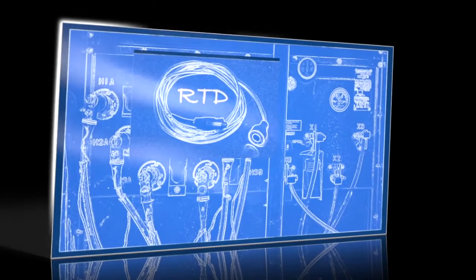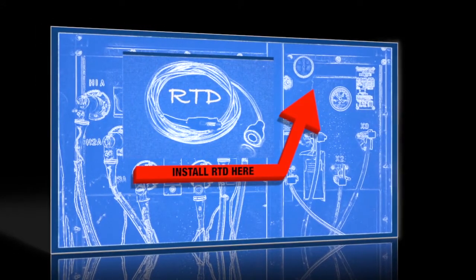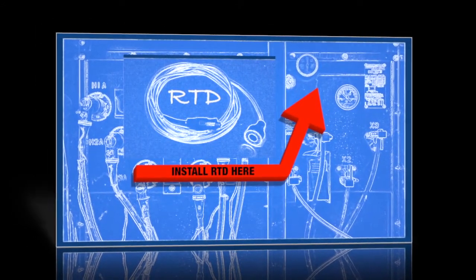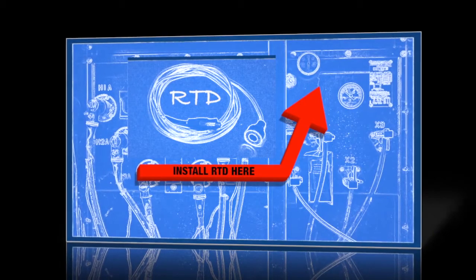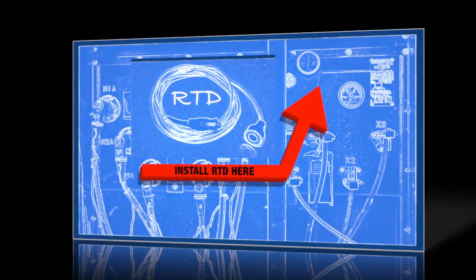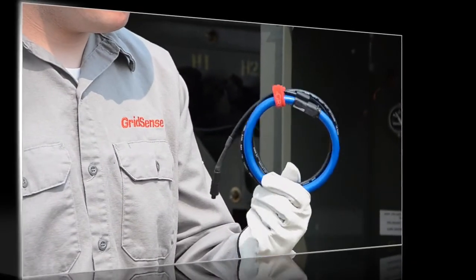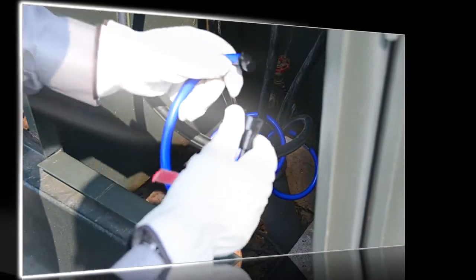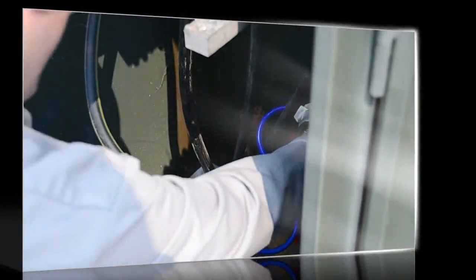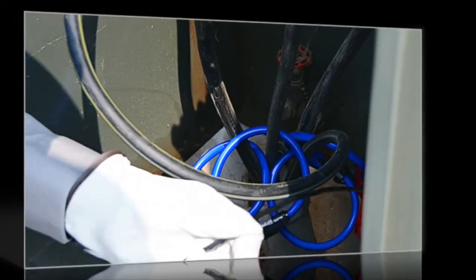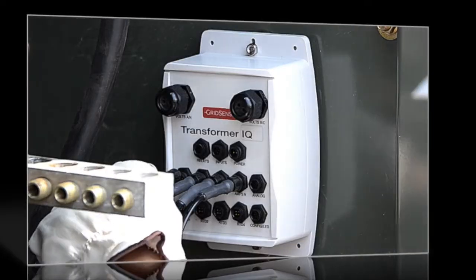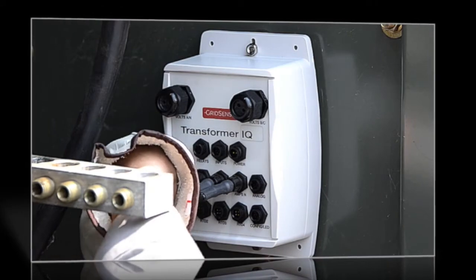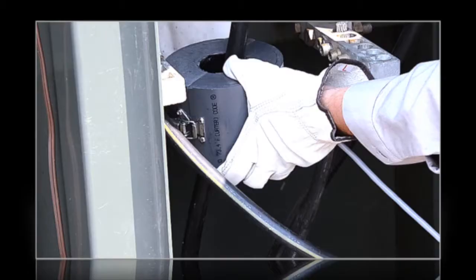You then attach the top oil temperature RTD to the tank wall. Of course, the RTD is attached to the appropriate input on Transformer IQ. Next, attach one Rogowski to each of the outgoing phases. Be sure to attach them in the right direction. The arrow must point in the direction of the load. The Rogowskis plug into the Transformer IQ unit.